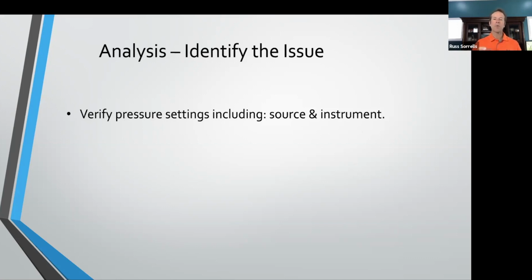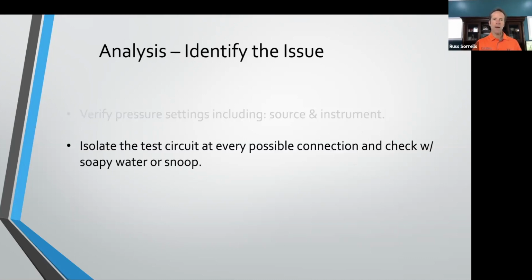But my point from a troubleshooting perspective is that oftentimes it is the pressure settings that are the issue. So it's important to just keep that in mind. We're going to talk a little bit more about how to set those in a minute. You want to isolate the test circuit at every possible connection, and then use soapy water or Snoop to determine if you can find a leak that way.